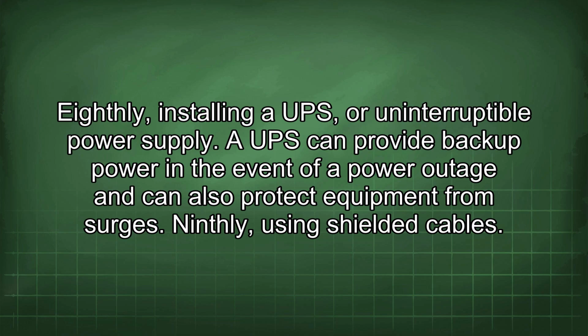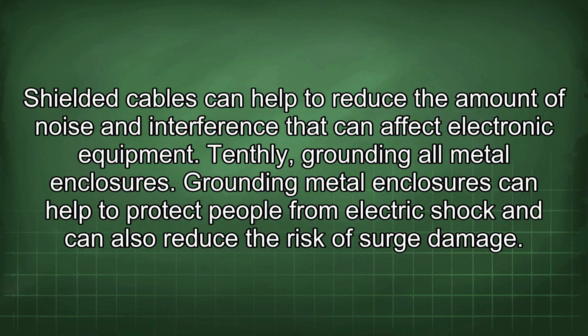Ninthly, using shielded cables. Shielded cables can help to reduce the amount of noise and interference that can affect electronic equipment. Tenthly, grounding all metal enclosures. Grounding metal enclosures can help to protect people from electric shock and can also reduce the risk of surge damage.